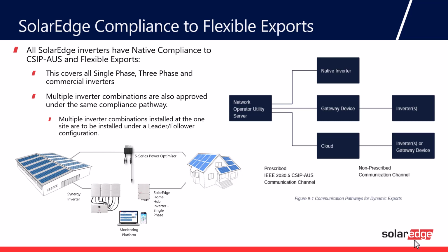That communication between the utility server and one of the devices is prescribed. What is non-prescribed is how, let's say, a gateway device would communicate with an inverter. So for all SolarEdge systems, we currently have the native compliance only, and that covers all of our single phase, three phase and commercial inverters, as well as multiple inverter combinations.